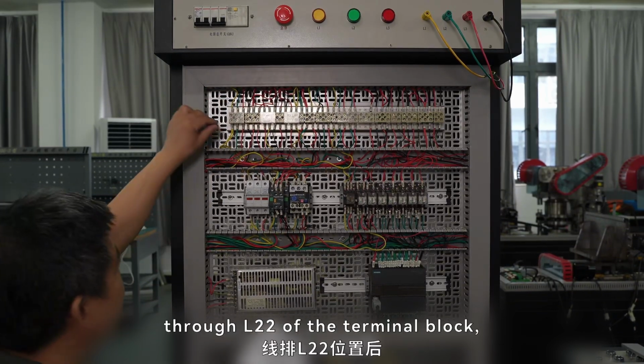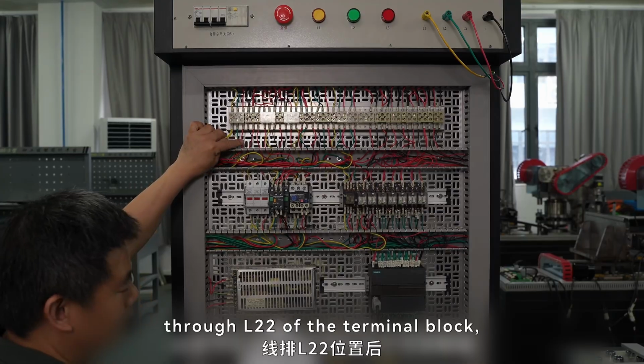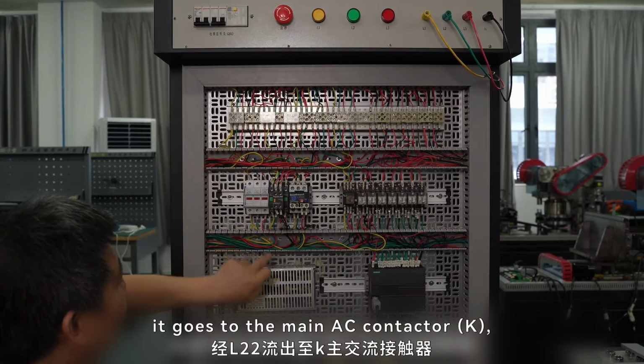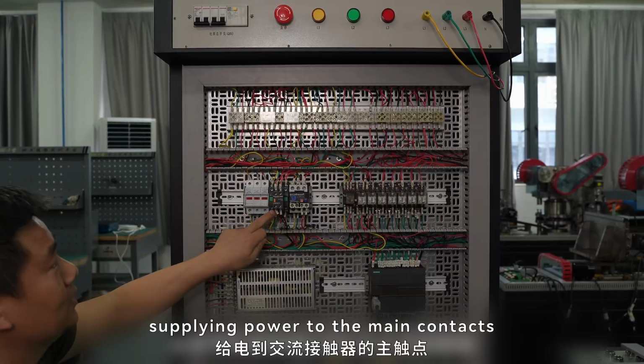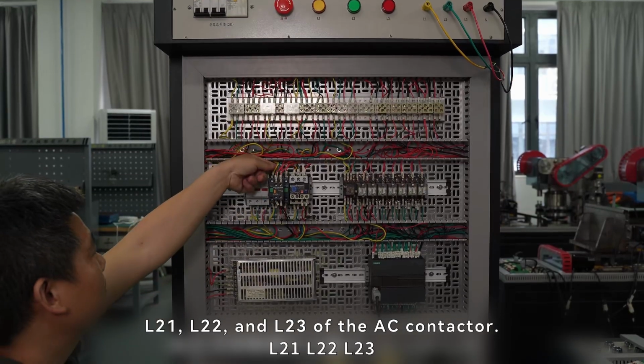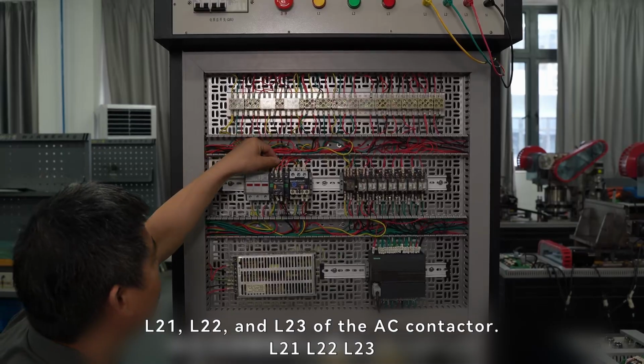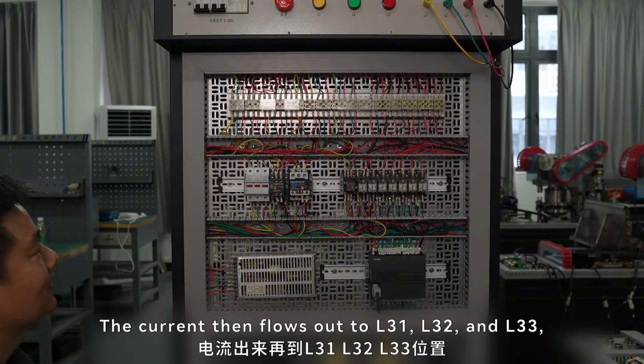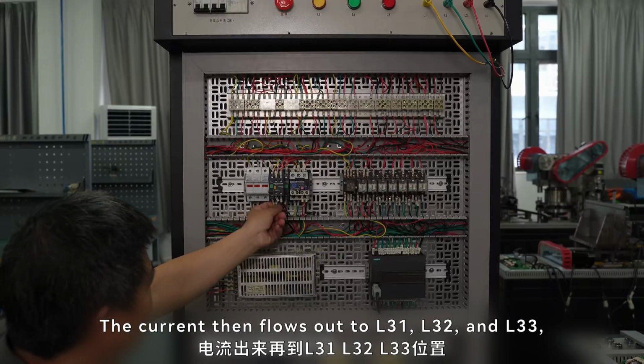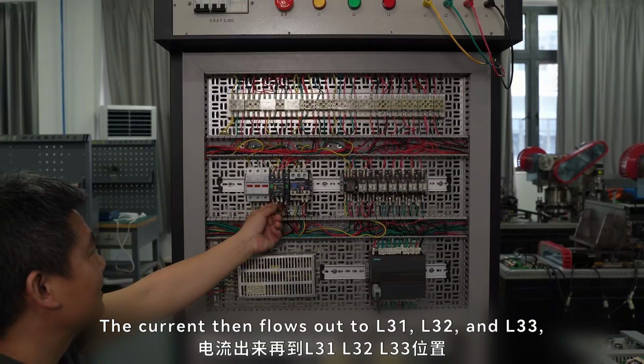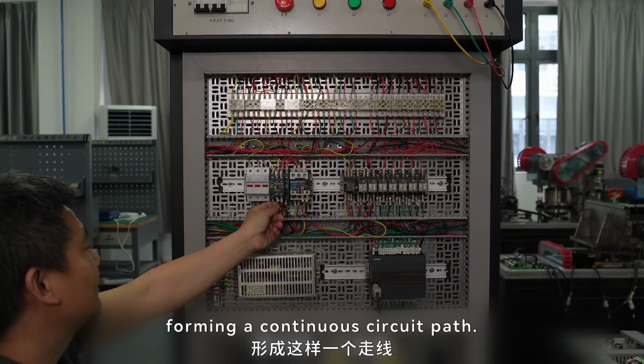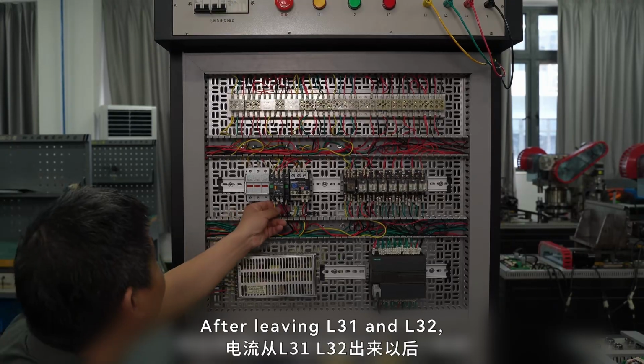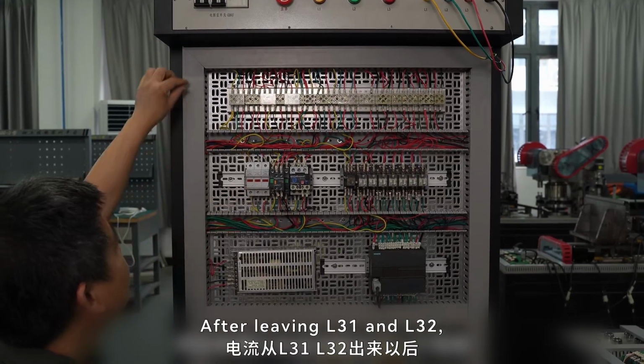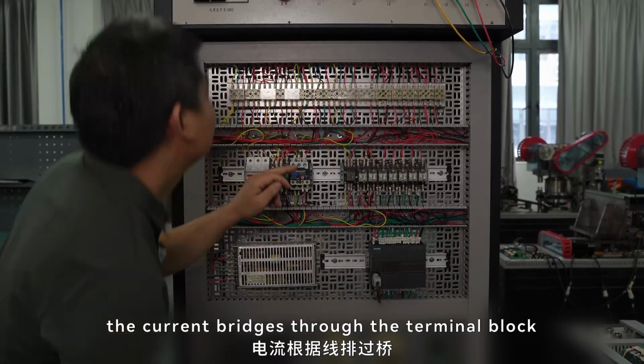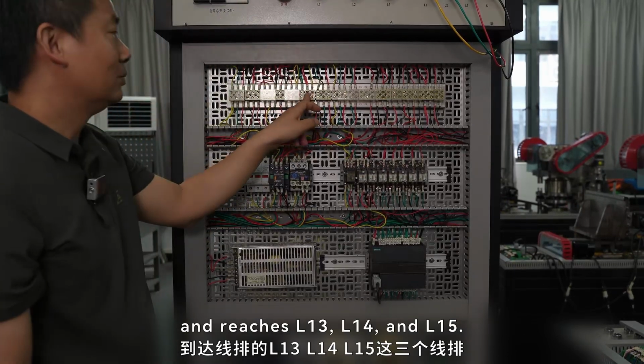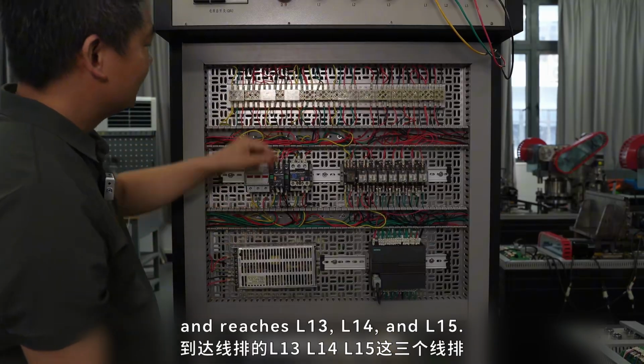After the current flows through L22 of the terminal block, it goes to the main AC contactor K, supplying power to the main contacts L21, L22, and L23 of the AC contactor. The current then flows out to L31, L32, and L33, forming a continuous circuit path. After leaving L31 and L32, the current bridges through the terminal block and reaches L13, L14, and L15.